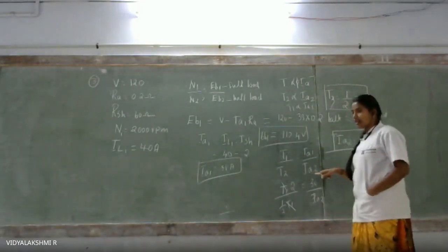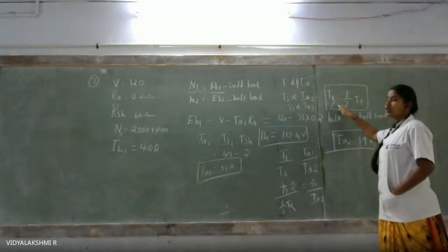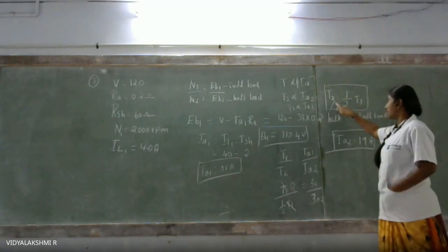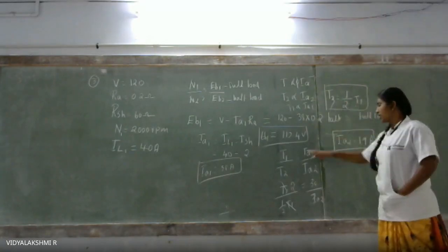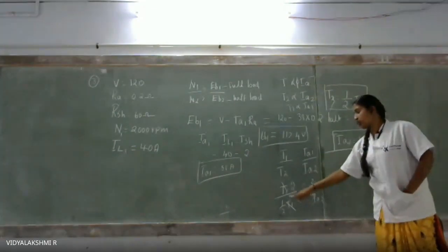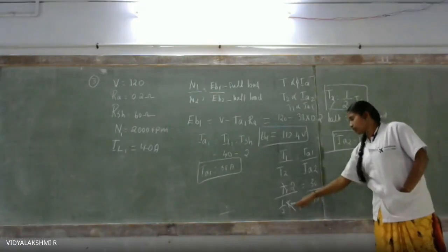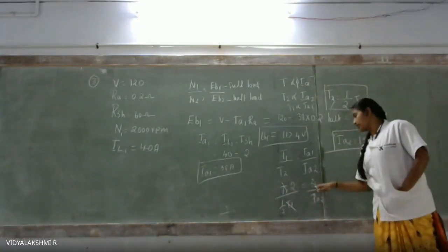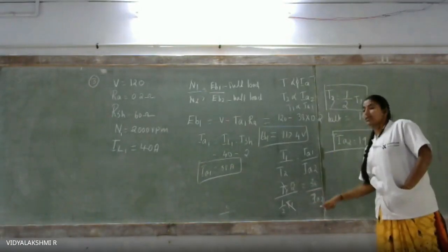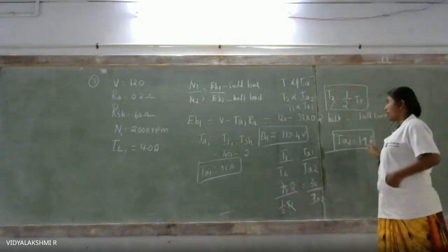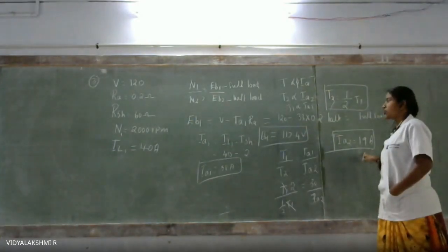So now I already said what is that? Full load, and half load is equal to half of the full load. So you can write it as T2 is equal to 1/2 of T1. I'm going to use the formula. So T1 by T2, we know T2 is equal to 1/2 of T1. So the T1 will be cancelled. The 2 will come to this side, and then 38 by IA2. So the IA2 will be this side. So 38 divided by 2 is equal to IA2 is equal to 19 amps. So now we know that 19 amps is equal to IA2.